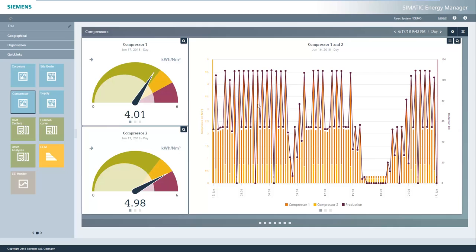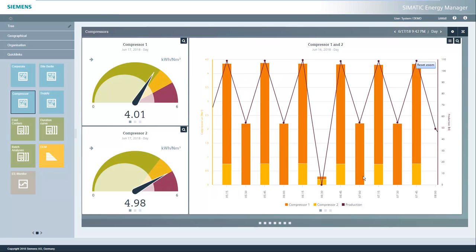The chart shows a comparison of both compressed air volumes in standard cubic meter, as well as the production volume in hectolitre. You can enlarge an area using the zoom function on the chart. In the diagram, compressor 1 is shown in orange and compressor 2 in yellow. Compressor 1 is used for covering the base load, while compressor 2 is only switched on in case of increased compressed air demand, as it is less efficient.